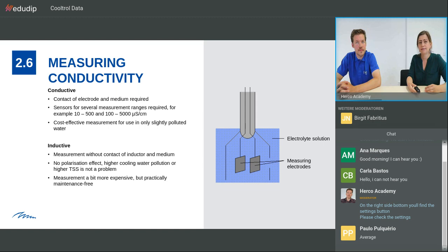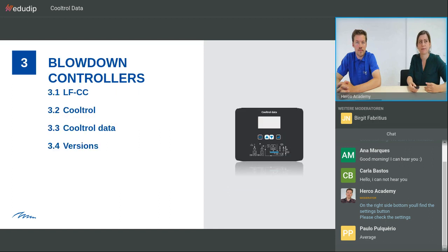That means it's very useful for slightly polluted water, but it can have problems because of the direct contact once the water is really highly polluted, has a lot of TDS, for example. In that case, an inductive measurement can be a better option. Here we have no polarization effect due to higher ion concentrations, and we can accept the higher cooling water pollution in general. This sensor, however, is then a bit more expensive, but there is also very little need for maintenance. So these are the two options that are offered.